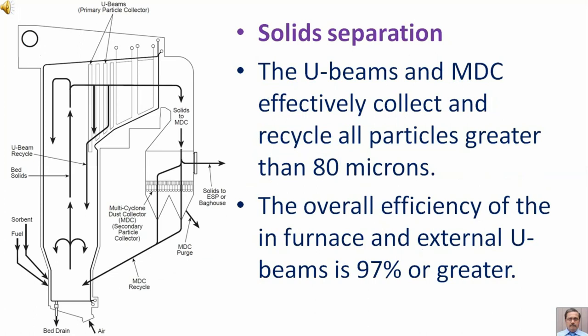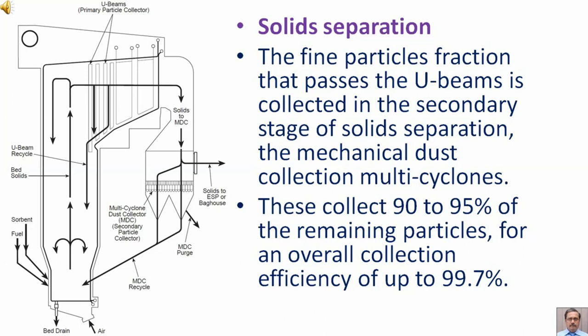The U-beams and MDC effectively collect and recycle all particles greater than 80 microns. The overall efficiency of the furnace and external U-beams is 97% or greater. The fine particles fraction that passes the U-beams is collected in the secondary stage of solids separation, that is the mechanical dust collection multi-cyclones. These collect 90 to 95 percent of the remaining particles for an overall collection efficiency of up to 99.7%.